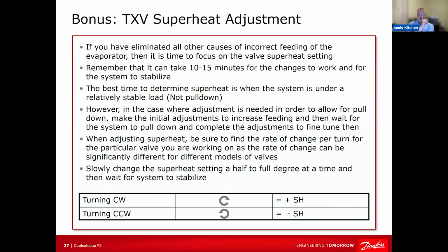But remember, it's very important to understand the rate of change of a TXV. We have a valve that we call the T2 valve. It's a brass body valve. It's got a stainless steel power head, cap tube, the whole 9 yards. It's been around forever. Its rate of change is 7, 8, or 9 degrees per turn. It is a very fast-acting refrigeration valve. Our TU valves, which are the stainless ones that you see, are about 4 degrees. If you go to the TR6, which is our AC valve, it's about 1 to 1.5 degrees per turn. So a massive difference, right?